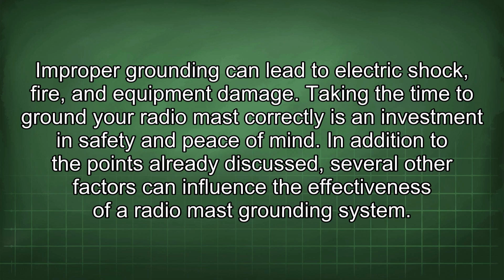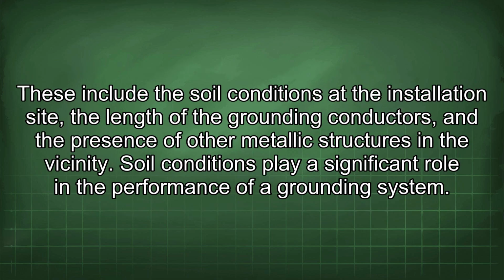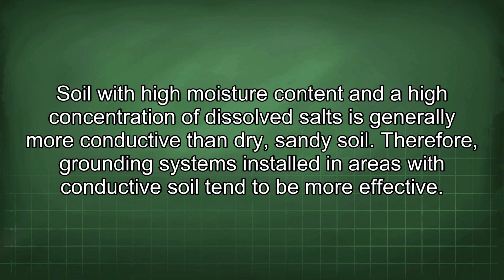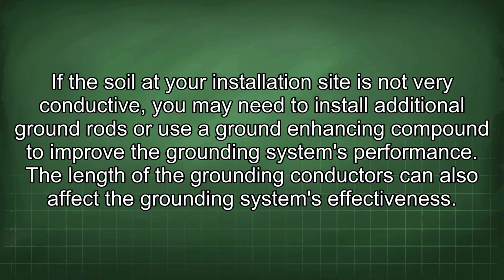In addition to the points already discussed, several other factors can influence the effectiveness of a radio mast grounding system. These include the soil conditions at the installation site, the length of the grounding conductors, and the presence of other metallic structures in the vicinity. Soil conditions play a significant role in the performance of a grounding system. Soil with high moisture content and a high concentration of dissolved salts is generally more conductive than dry, sandy soil. Therefore, grounding systems installed in areas with conductive soil tend to be more effective. If the soil at your installation site is not very conductive, you may need to install additional ground rods or use a ground-enhancing compound to improve the grounding system's performance.